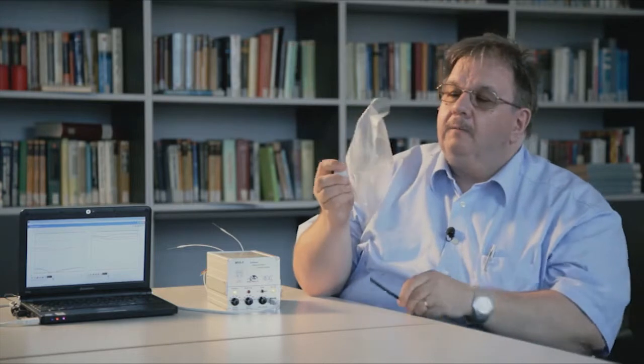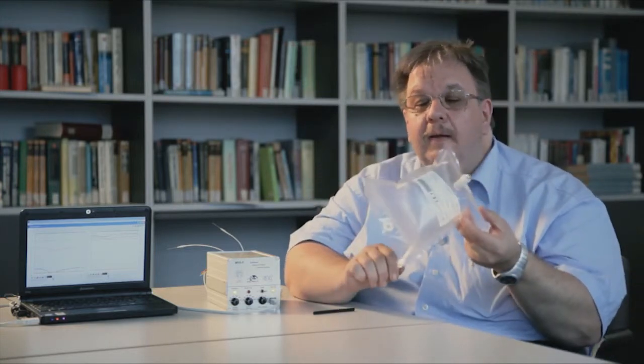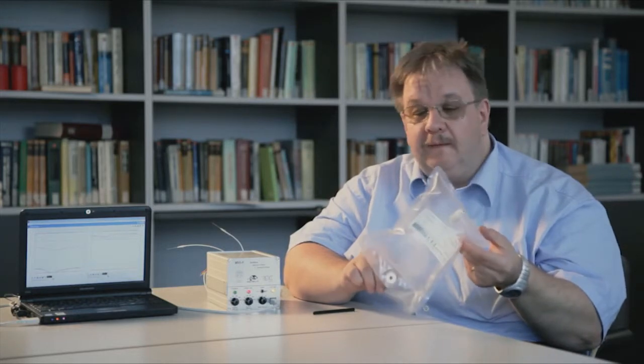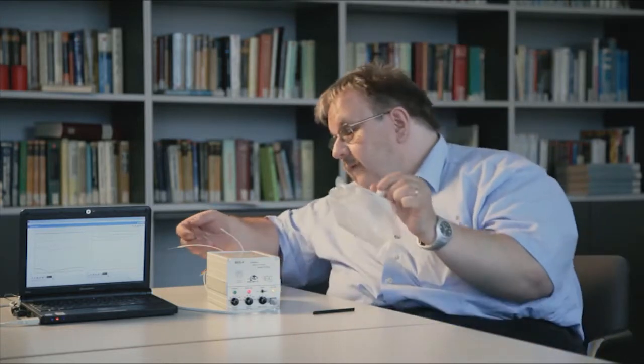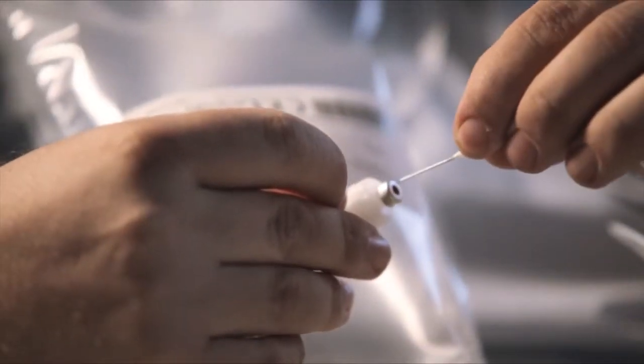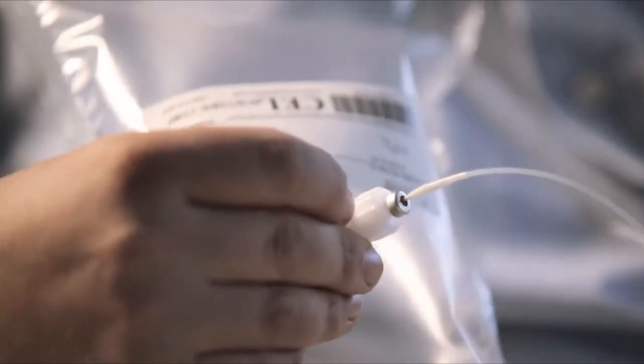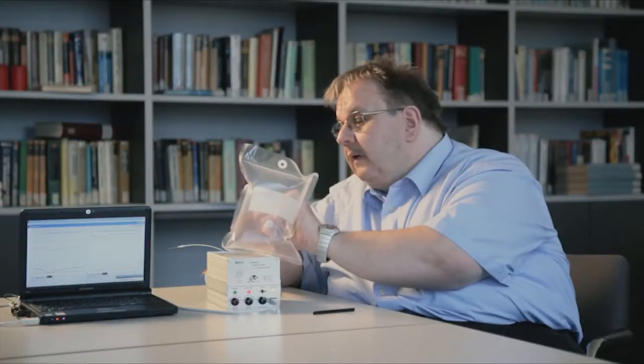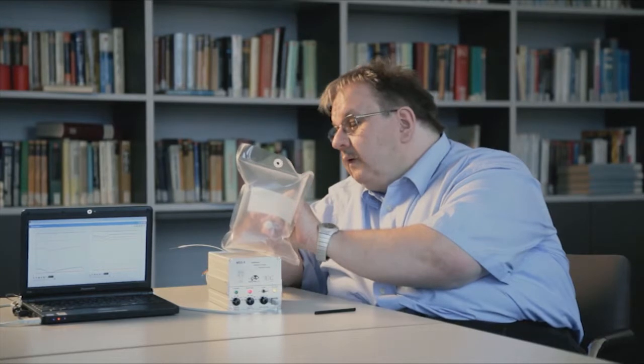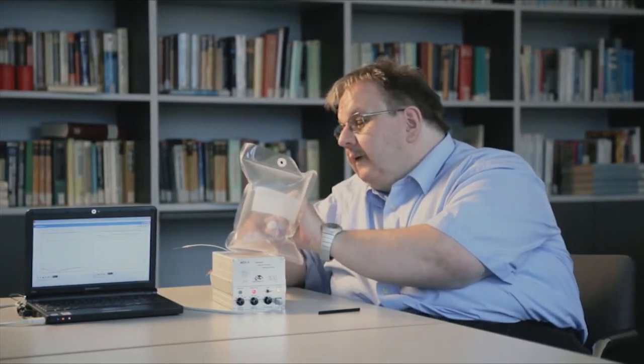Okay, so this is about 1 liter of breath in this bag, and you see it is a completely non-invasive method. So this will not harm a patient, it will not take blood or anything else. So it is really a non-invasive method to investigate diseases using the breath of a patient. So this bag is now being connected to this little tube here with the injection needle, and then the breath is being transported by a micro pump into the sensor chamber, which is inside the box.